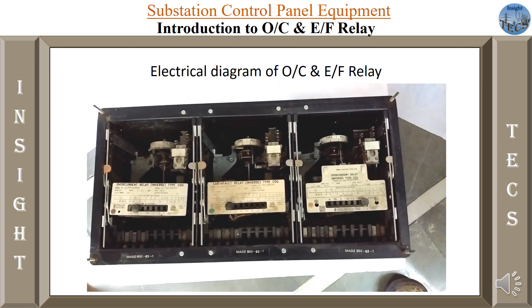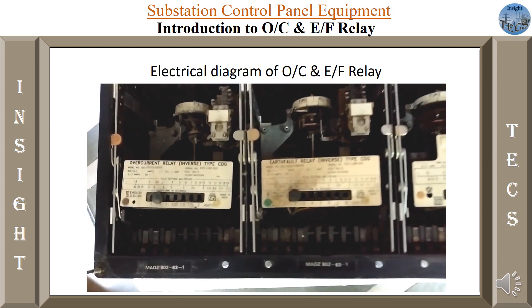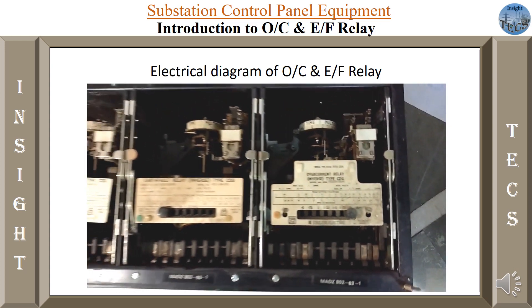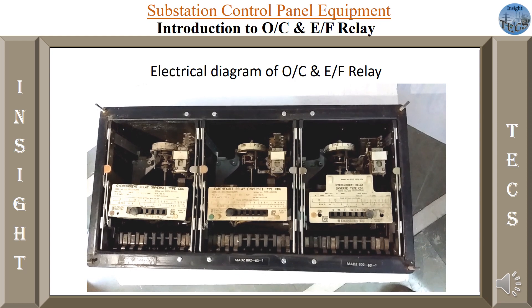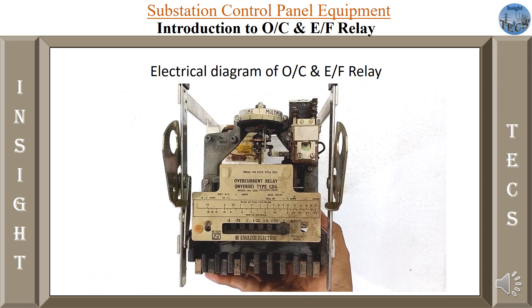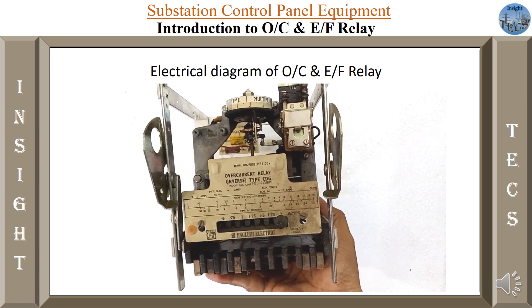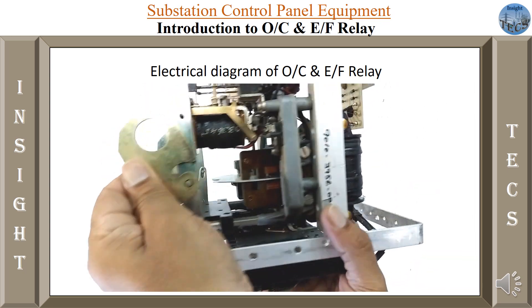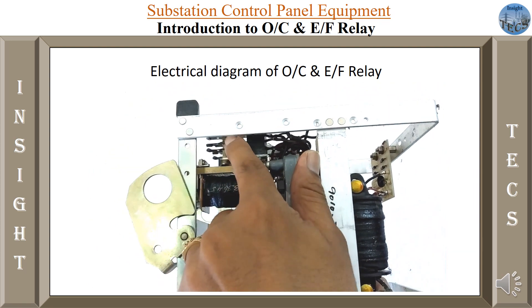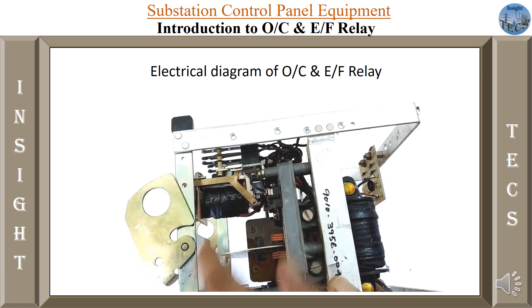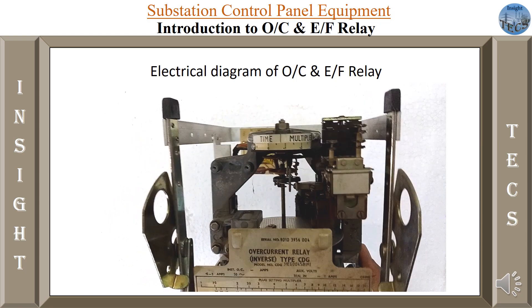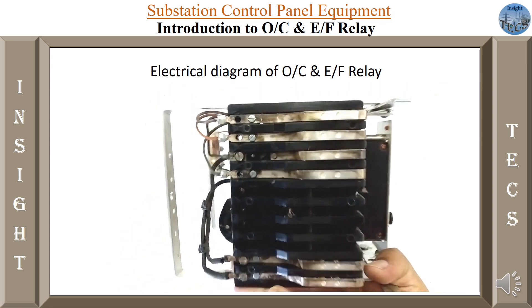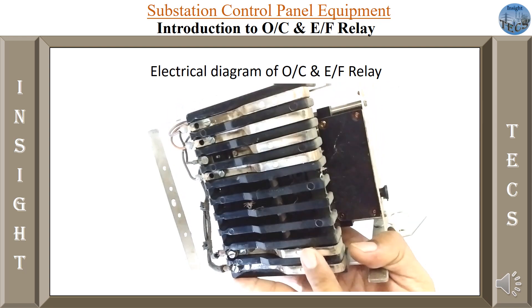This is how the basic over current and earth fault electromagnetic relay looks. It has basically three relays — two are over current relays and the middle one is the earth fault relay. Taking out a single unit — one over current relay for one single phase — you can see the operating coil, and it has contacts connected to the breaker or through a master relay towards the breaker. The input is given through the CT terminals.